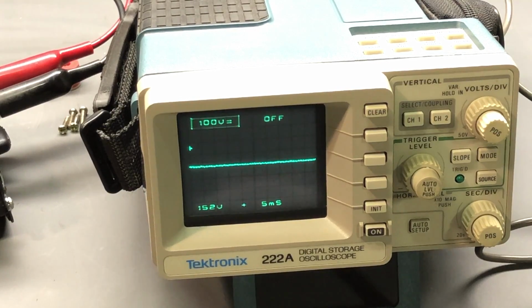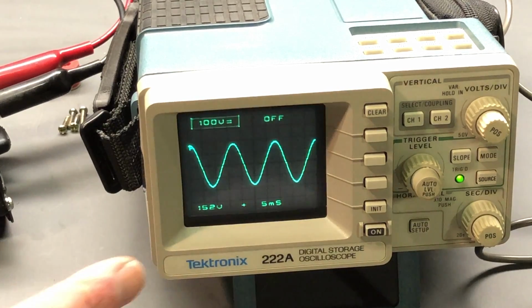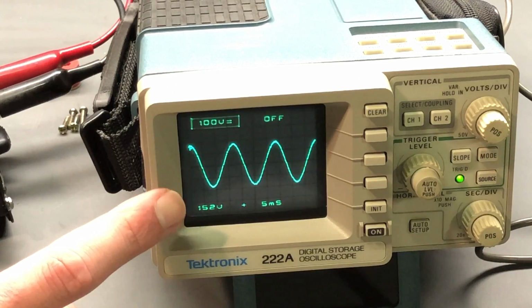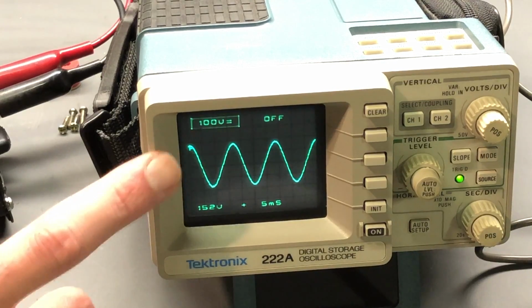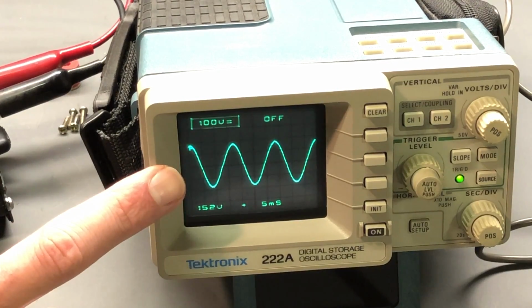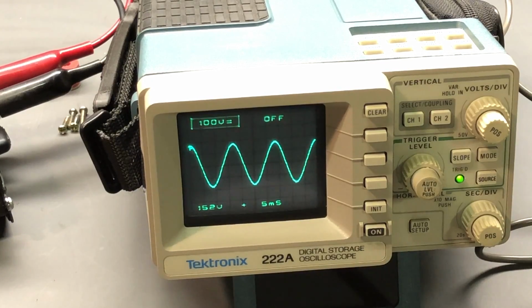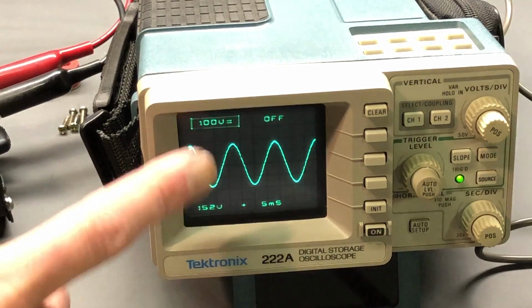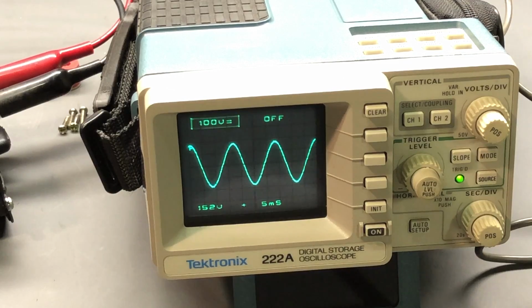So I'll turn the power inverter back on again. There we go, and we do in fact have an equal amount above and below that ground reference, so that looks very good. Looks like a stable waveform, no distortion. So that's looking very good, no issues with that whatsoever.